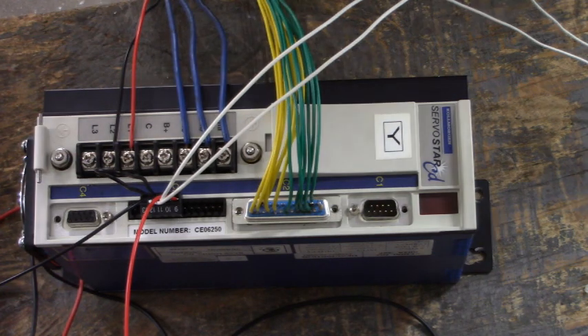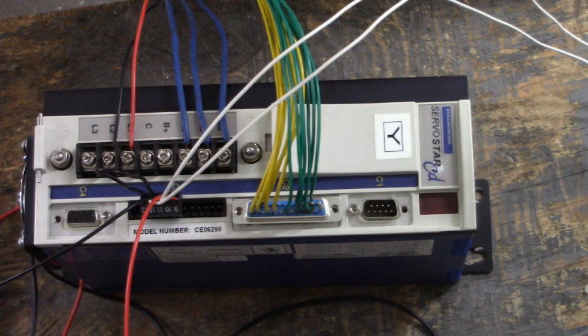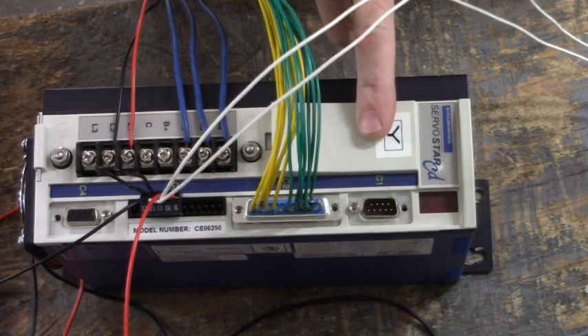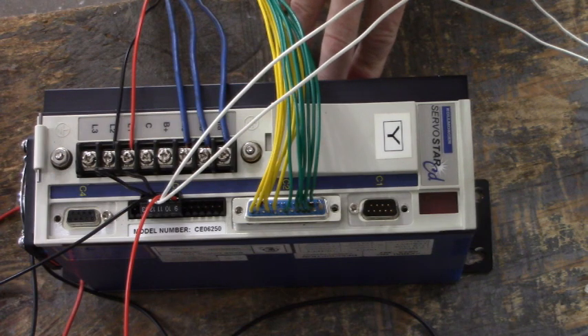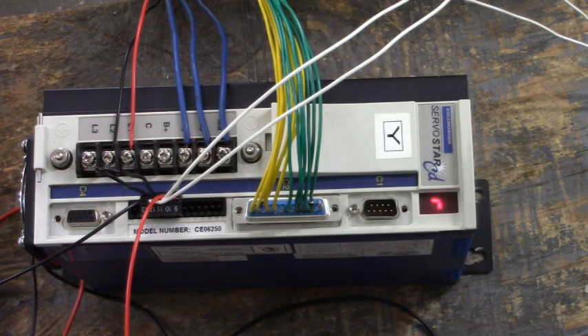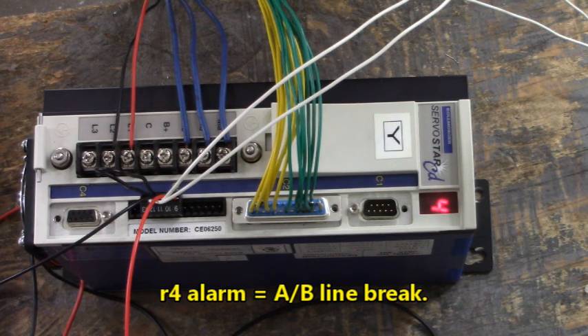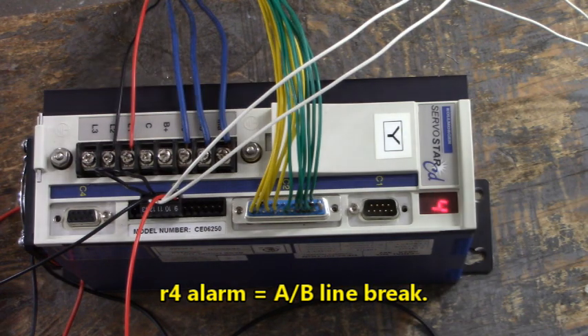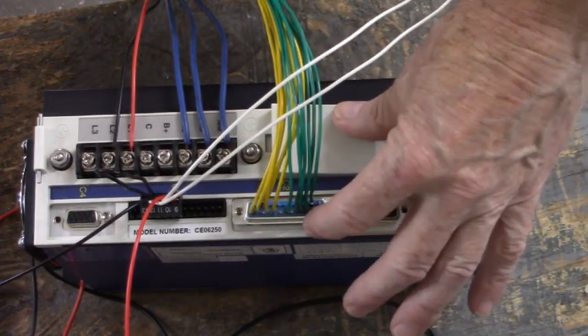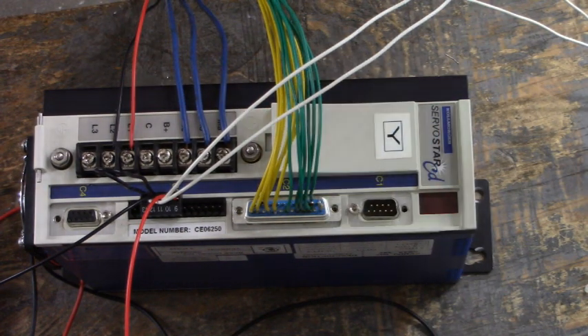Now we're going to take a look at a few alarms that you might encounter with this servo drive. I've got my Hall Effect incremental encoder simulator turned off. We're going to apply power to the drive, and you can see it boots up to R4. Let's go see what R4 is. R4, AB line break. Break in encoder A/B input lines detected. So we have no encoder or Hall Effect input to the drive from the feedback.